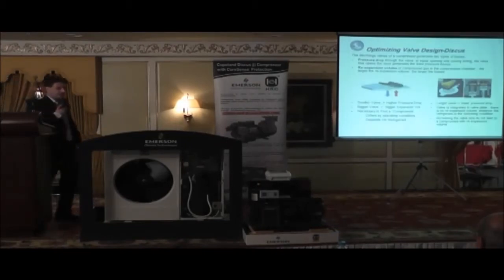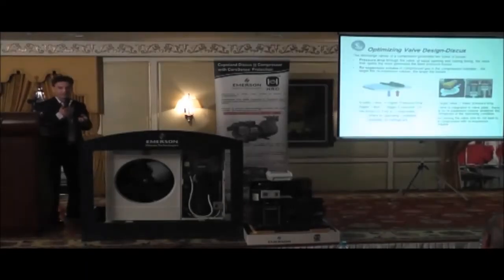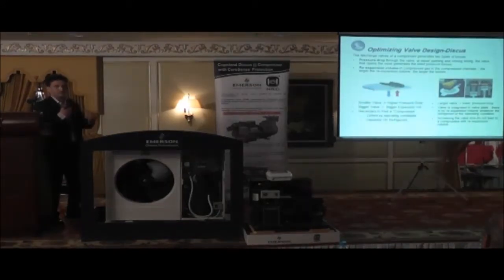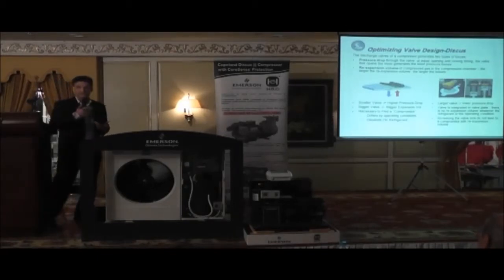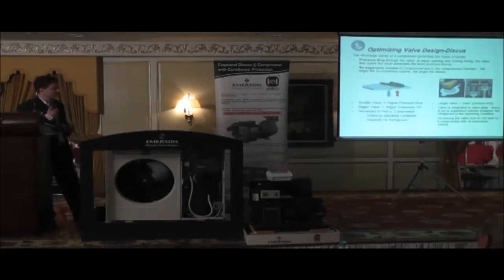So these are the modifications we've done to the discus valve. You can see that if we go with a smaller valve, we have a higher pressure drop, and if we go with a bigger valve, we have a bigger expansion volume. So these two work against one another. You've got to find a compromise between the two if you want to achieve the best efficiency out of the compressor. And the way we are doing that is with discus technology.